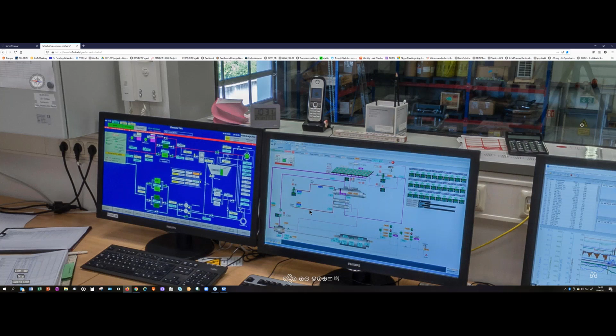You spoke before about monitoring the brine. What do you monitor regarding the brine? Basically the brine is constantly analyzed, completely analyzed once a year. We have a chemical consultant with a special testing device, so we are able to sample brine on the hot and cold side, on the production and reinjection side. Once a year we receive a complete analysis of the brine, all the necessary values, not only the gas content but also the mineral contents. As we are partnering in several R&D projects, we have further sampling procedures over the year, and therefore a very interesting and broad database for our brine over the last 10 years.